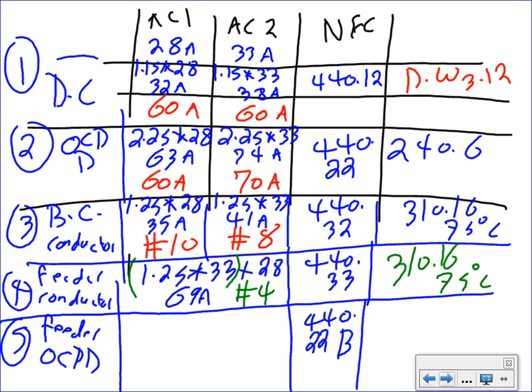If you read through B, we went to 440.22A when we calculated the branch circuit. When we calculate the feeder, we go to B. It says the overcurrent protection is the same as for a motor: the largest overcurrent protection device of the system. What's the largest overcurrent protection device of the system?